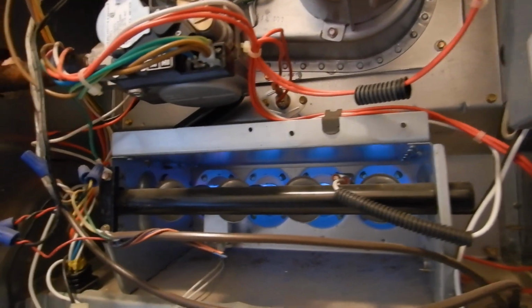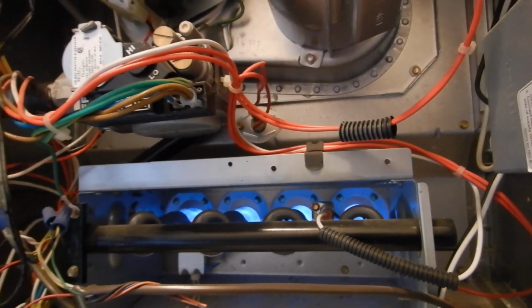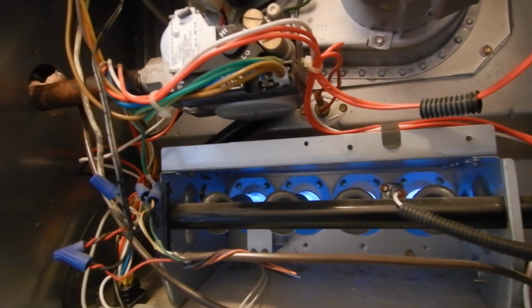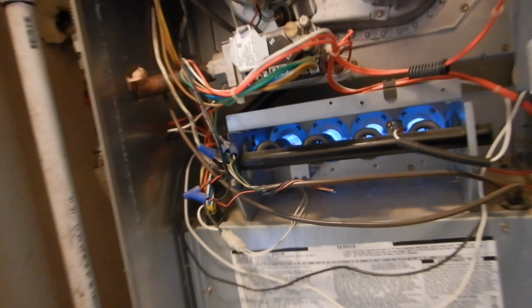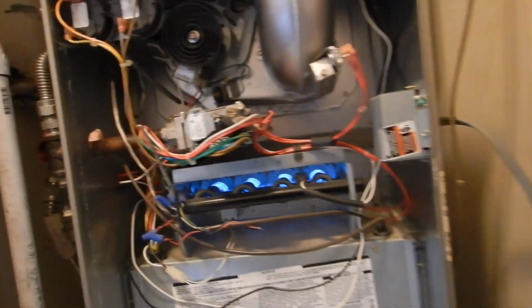Okay, kind of a rough start. Get some feathering in there. Not seeing any yellow though. Oh, we got a little splash over here on the right, the right jet. I'd call that fair. We're going to use the carbon monoxide detector on this, just because it's so shaky.